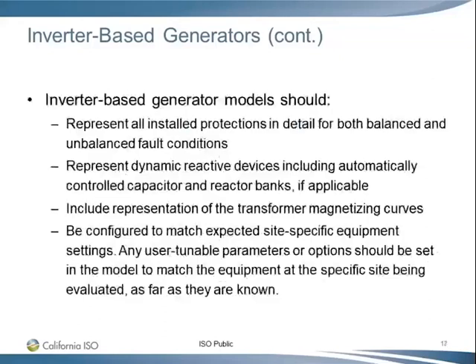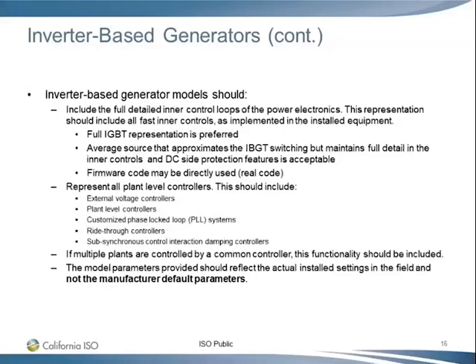And also, if multiple plants are controlled by a common plant controller, we want to see that. Our model request is going by resource. Each individual resource receives one model request, and you submit a model for that resource. But it's possible you have several resources inside the same plant, and they are under some common control. If that happens, you should indicate that. And you may even just submit the whole thing together, several resources, as long as we are clear which one is which. And also, I emphasize this one more time: parameters should match what's installed in the field, not manufacturer default. Next slide, please.